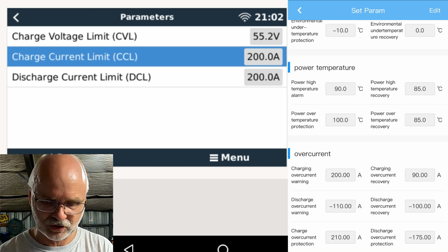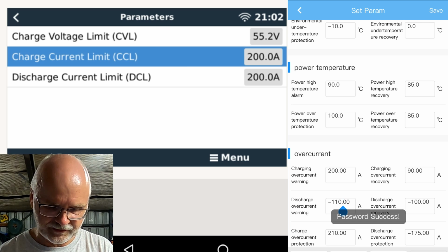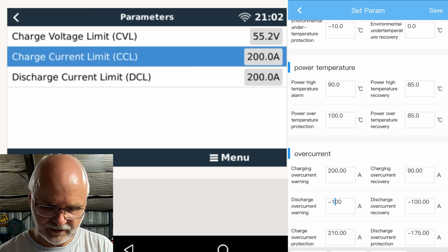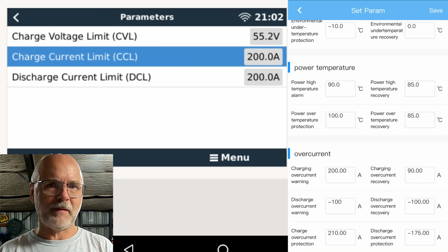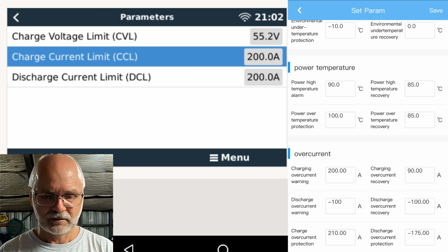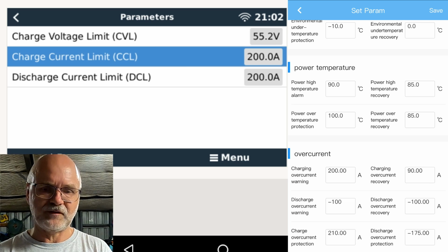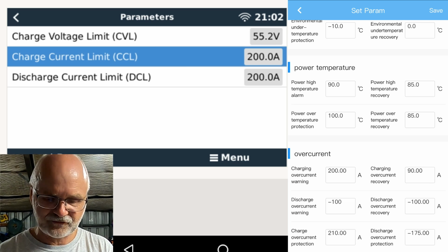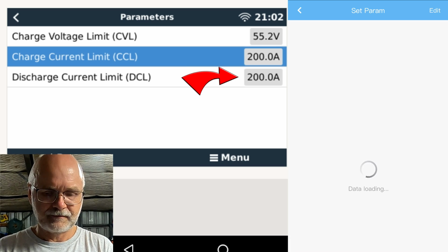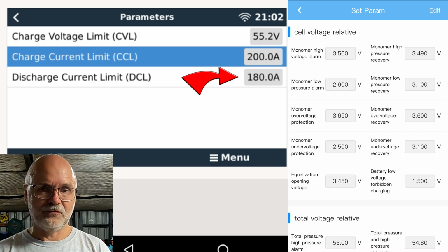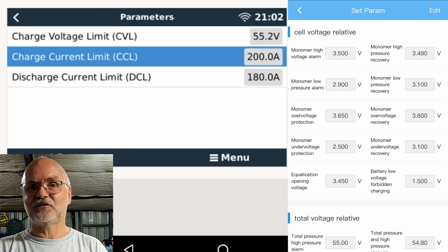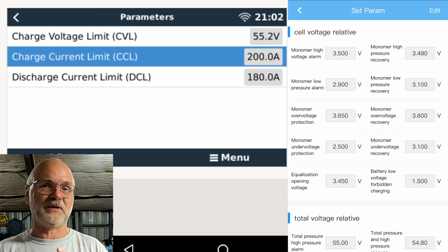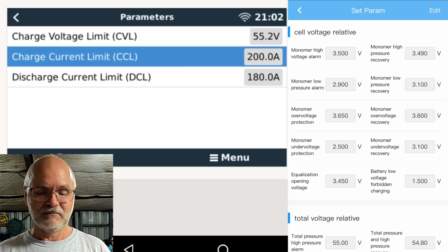the Victron system shows. So if I change this parameter and set this one to 100, for example, it's 100 minus 10 is 90 times 2 is 180. So the discharge current limit in the Victron system should change to 180 as soon as I save this one. Bang, 180. So that's how you change the parameters in the Victron system, and the Victron system will only follow what the BMS requests or demands or wants. I link all these formulas on the website. There's the link down under the video for that.